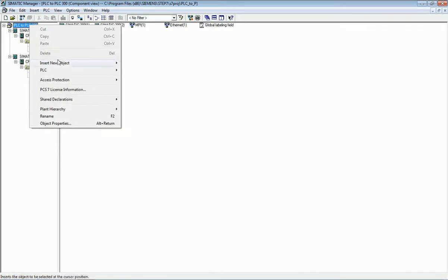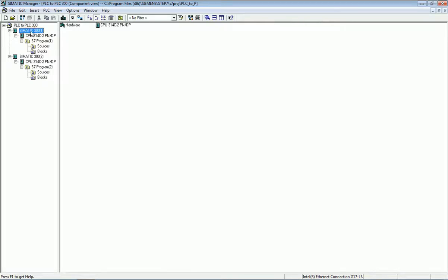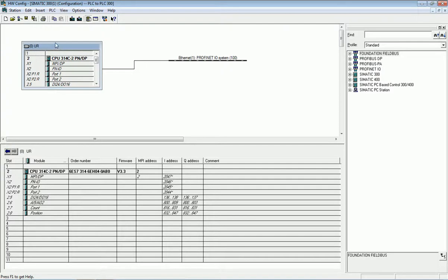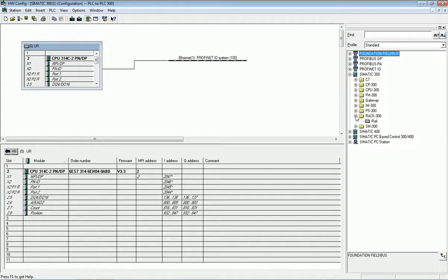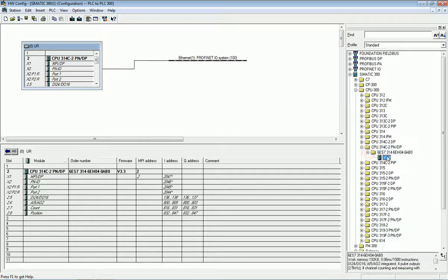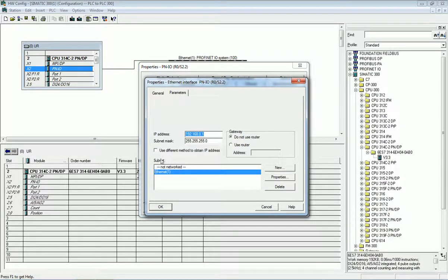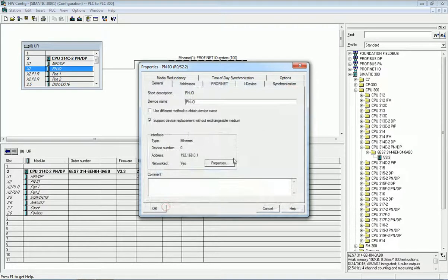By right-clicking on the project you can go to New Object and add a PLC station. Then we go to hardware configuration. In hardware configuration you can take the rack from the options — you will get a rack or rail for the S7-300 PLC. Then you select the CPU as per your hardware. We are using CPU 314C-2 PN/DP. I have drag-and-dropped this PLC hardware into the rack. Here you can define the IP address for the PLC. I have added one subnet named 'Ethernet'.